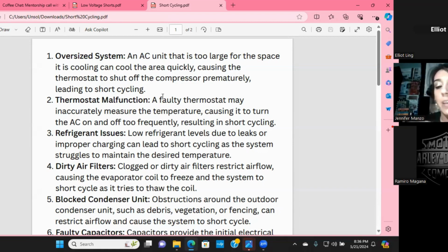So these units, if they run, say, for an hour straight, you have the best possible dehumidification going on that you can possibly get. If it runs for 5 minutes and hits set temperature and then shuts off, the humidity is still building, even though the temperature, especially in a tight house, is staying the same. So in leakier houses, you don't have this problem as often, or it doesn't become as noticeable. But when it comes to newer homes or new construction, we end up with very tight homes and the temperature will drop much faster than the humidity.